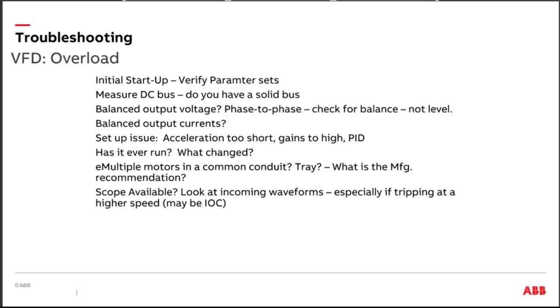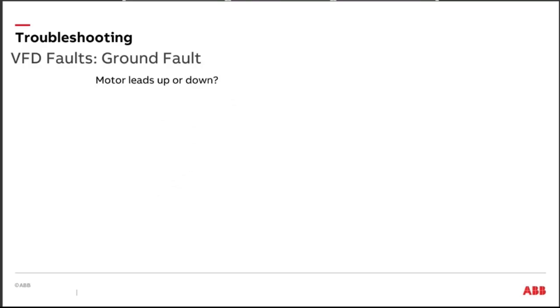That's one of the really neat things about an active front end drive or an ultra low harmonics drive. We're not so dependent upon the shape of that voltage waveform coming in. Ground fault, and I apologize for talking fast. I'm just trying to get everything in for us here today. Ground fault, I always like to look, and my daddy was a coal miner, so I always like to look and see if my motor leads are going up or my motor leads going down.